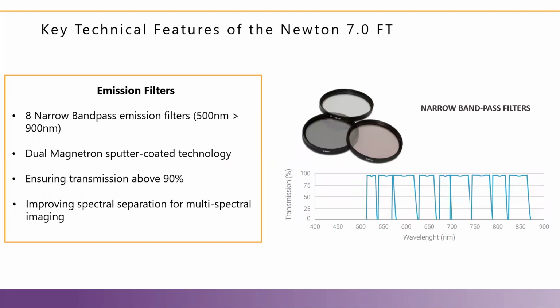There's also a dual magnetron sputter-coated filter technology, which will ensure transmission above 90% and very narrow band cutting for improved spectral separation and increased sensitivity. So this will be important for those of you interested in doing some spectral unmixing, looking at multiple fluorophores within the same animal, for example.